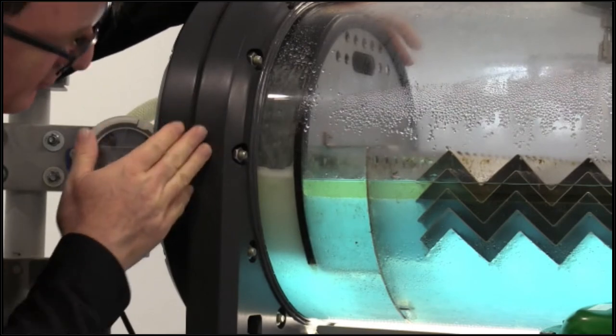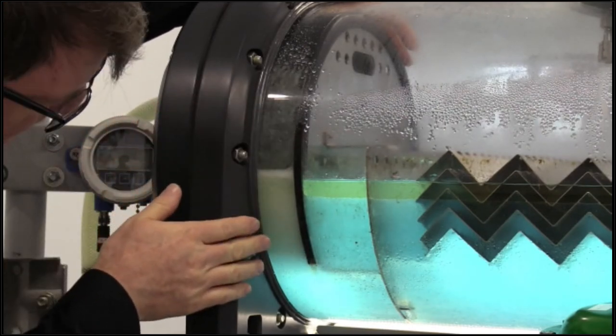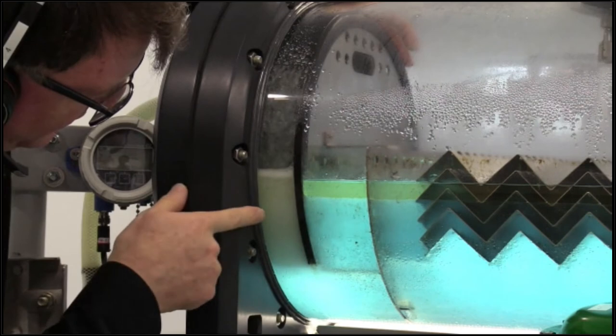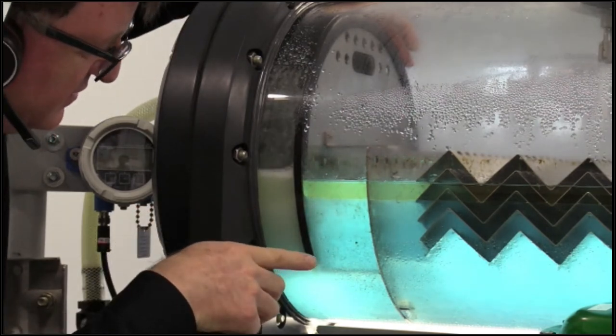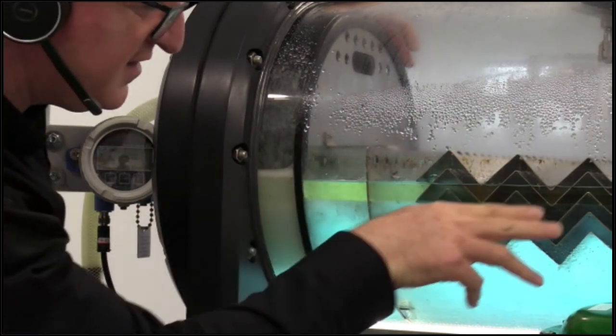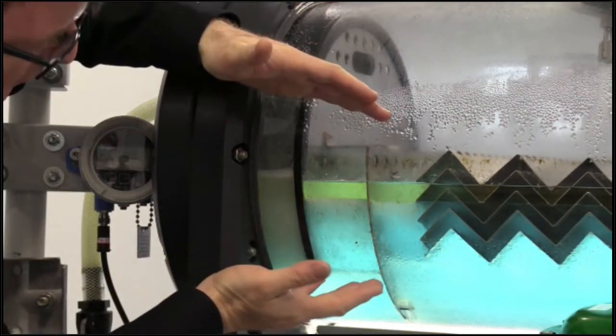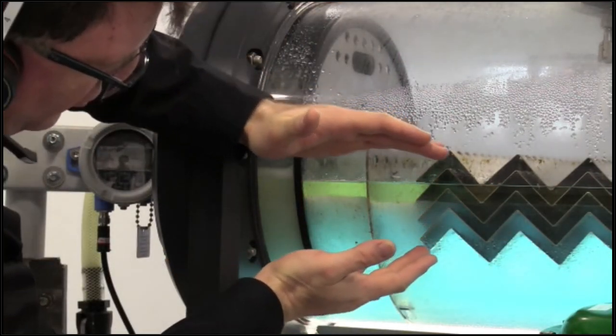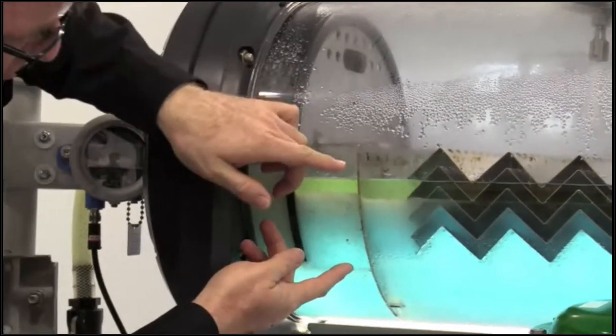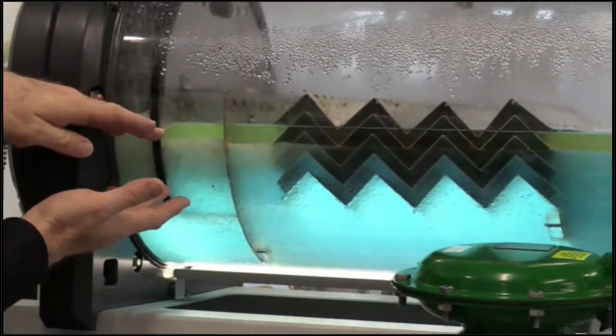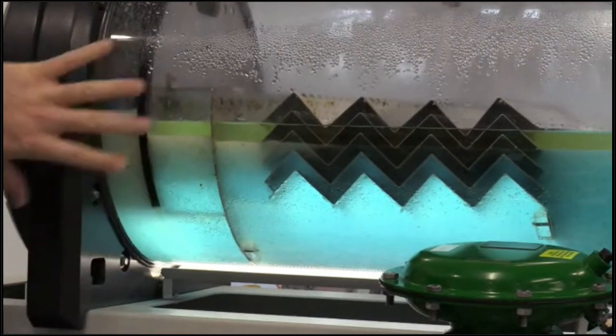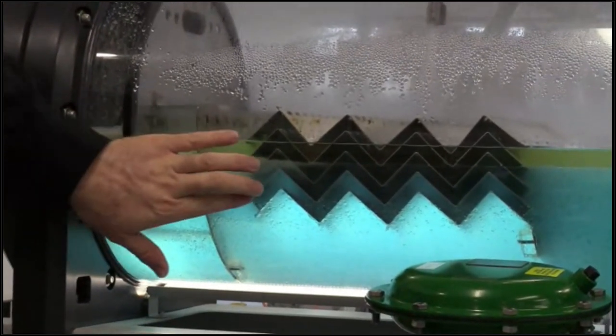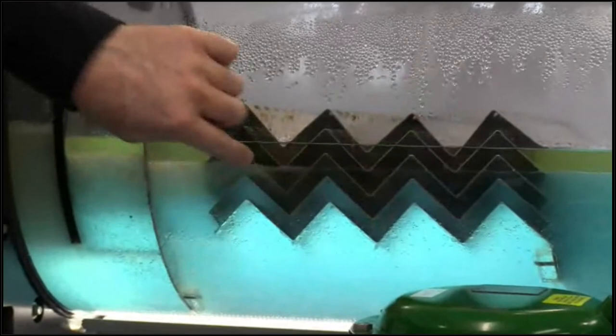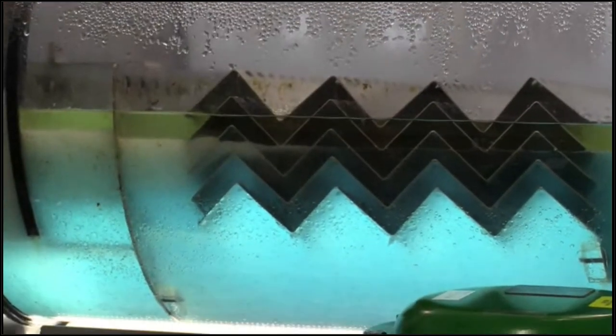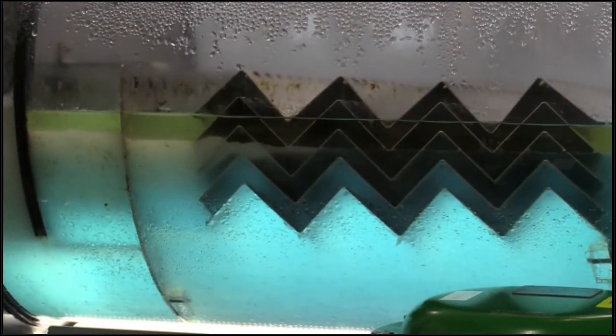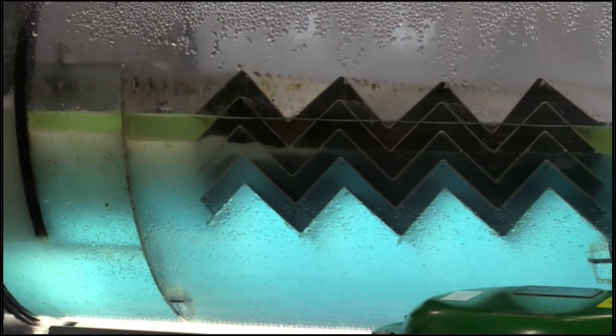So now we're going to start dropping it down. The first part is going to make a large separation. Then we're going to go through the coalescent plates, and we're going to see how our profile is going to be created here. So here we're going to see basically emulsion, a little bit of oil, a little bit of water, and gas in the middle. And the three elements are going to be separated with the coalescent plates. So here we can see that the densities and the gravities are making the large part of the work.